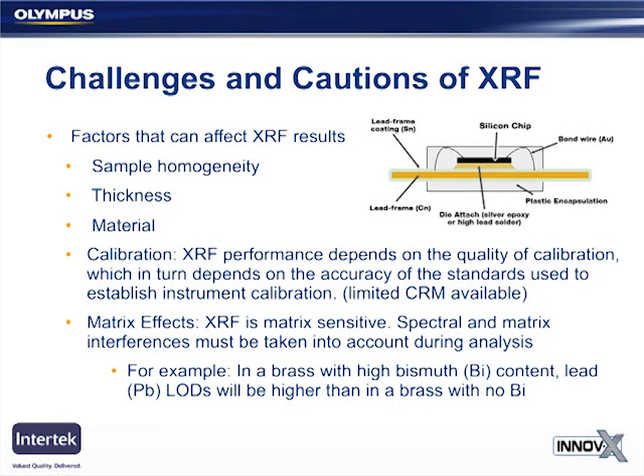It's also very helpful to understand how your instrument is calibrated. XRF instruments usually come with several factory-installed calibrations for different material types, and so you may need to validate that calibration on your own sample types. Now, you can do this with reference materials, certified reference materials, or CRMs for your sample type, but there are a limited number of CRMs suitable for XRF compared to the volume of different sample types that people want to test with XRF.